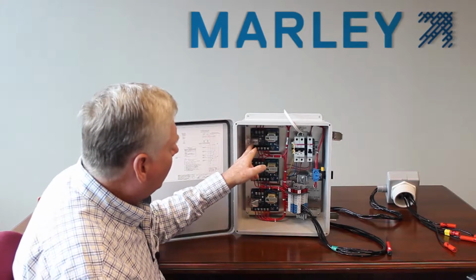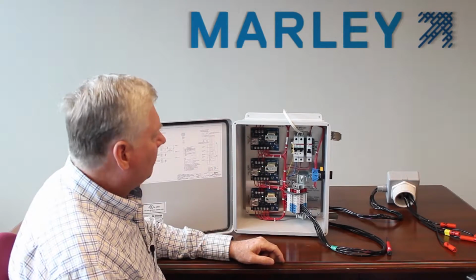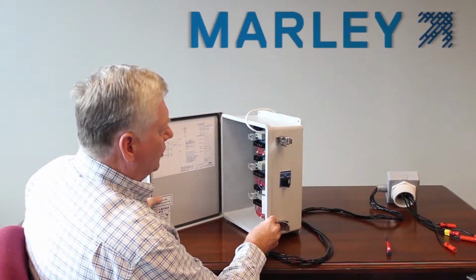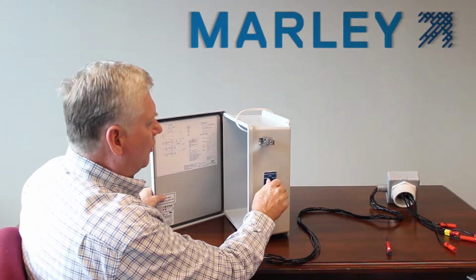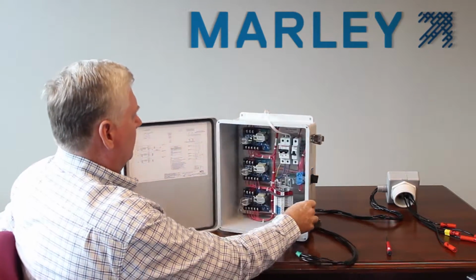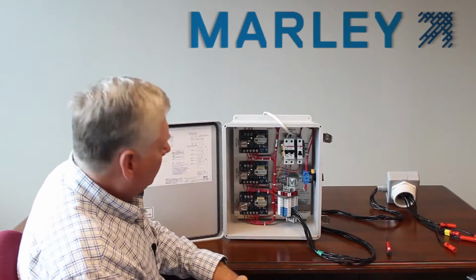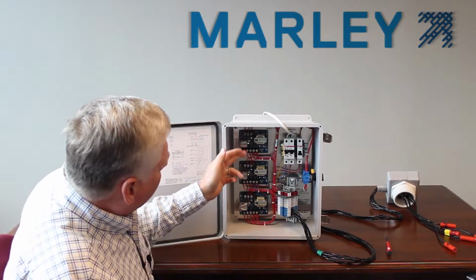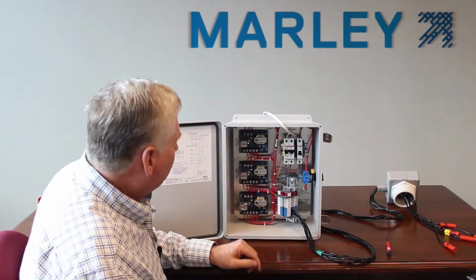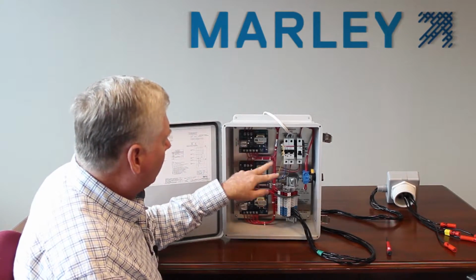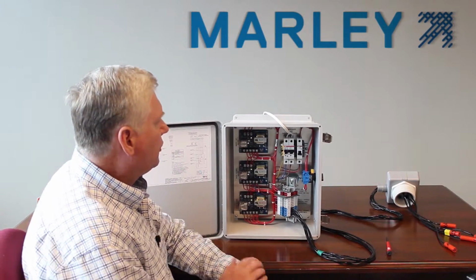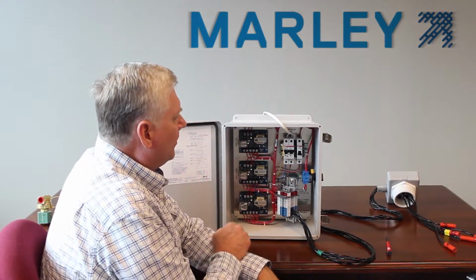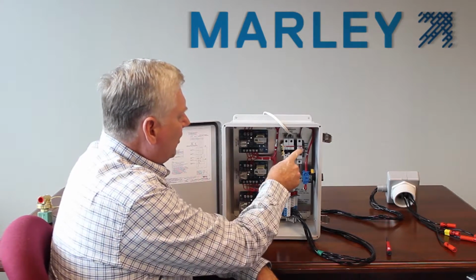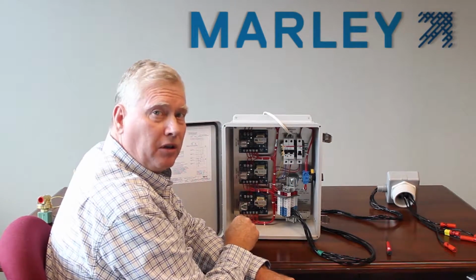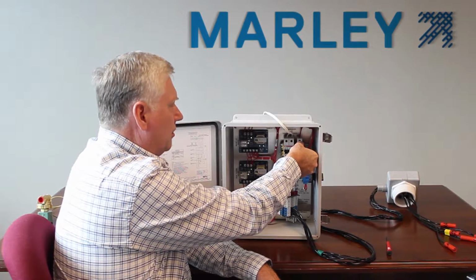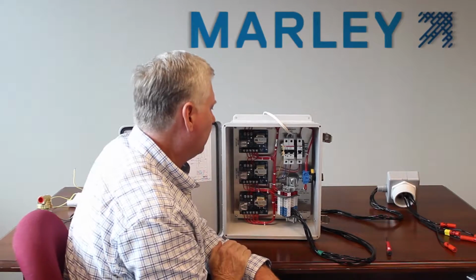Now if you notice on the makeup card here, I don't see a light. That is because my HOA selector switch is off. So if I turn that to the automatic position, now my light comes on. So I can visually see that all 3 cards are receiving power. That tells me all this red wiring at this point is correct within the system. The other circuit breaker is for the makeup right here, and this provides power to the customer's remote solenoid. So you have to make sure it is also turned on. Otherwise your solenoid is not going to operate.